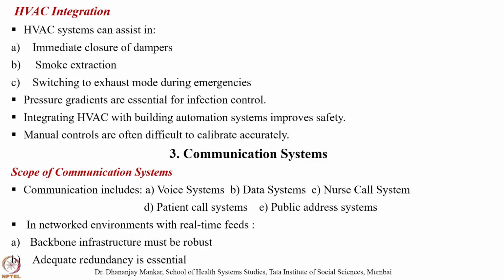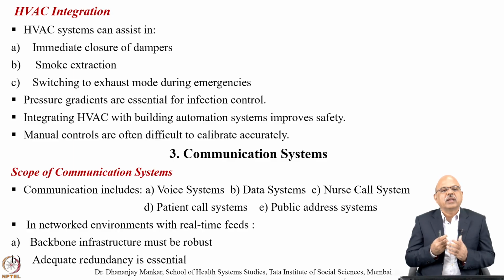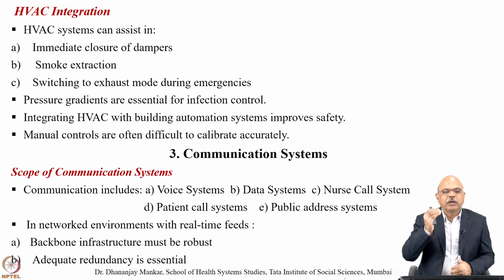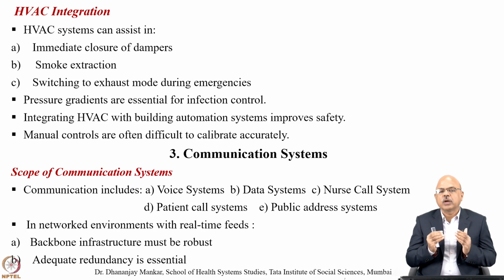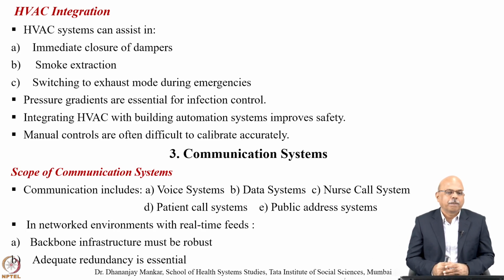Now for HVAC integration. HVAC integration systems can assist in immediate closure of dampers, smoke extraction, and switching to exhaust mode during emergencies. Pressure gradients are essential for infection control, and integrating HVAC with the building automation system improves safety. Manual controls are often difficult to calibrate accurately.